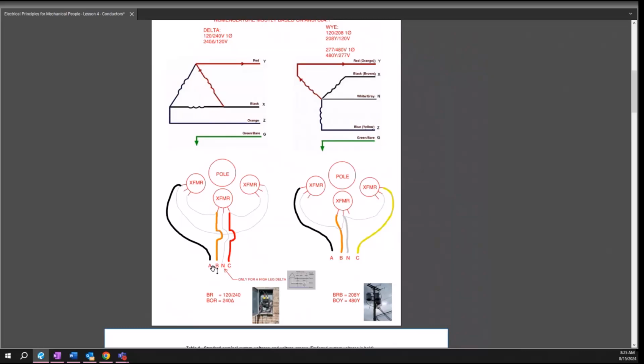To me, it's no different than doing an open delta. An open delta is when you don't have the third transformer but still have 3 phase. It's called a ghost leg. Most of the time you can actually see a larger transformer and a smaller transformer, with 4 wires coming off the pole.